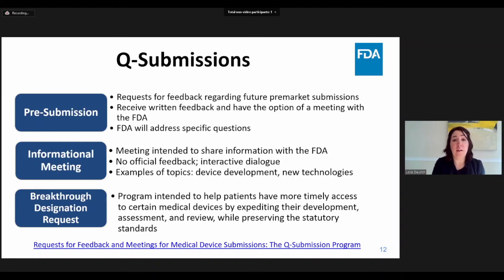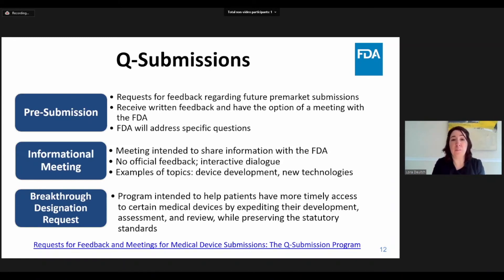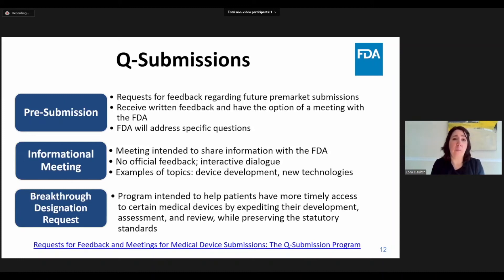For example, if you're planning on conducting an IDE clinical trial for your significant risk study, a pre-submission meeting is a way to receive feedback from the FDA on your draft clinical protocol. An informational meeting is a type of meet-and-greet in which the sponsor intends to share information with the FDA. This is often used for new technologies to allow the FDA to become familiar with the device prior to a pre-submission or pre-market submission. There is no official feedback; however, there is often interactive dialogue during the meeting.